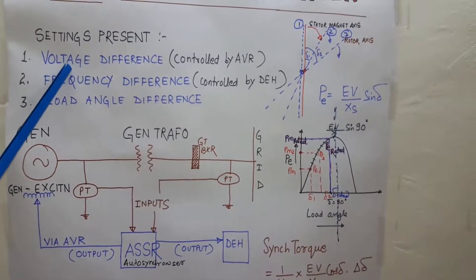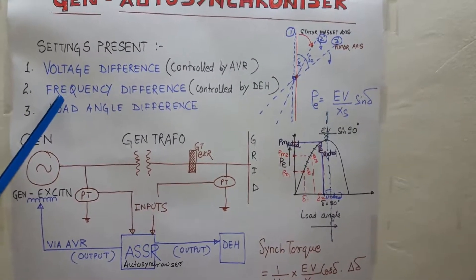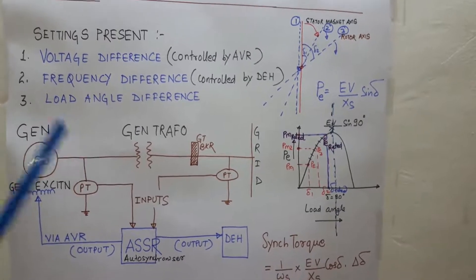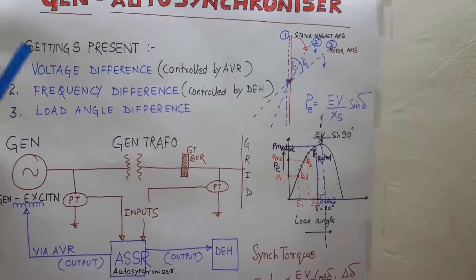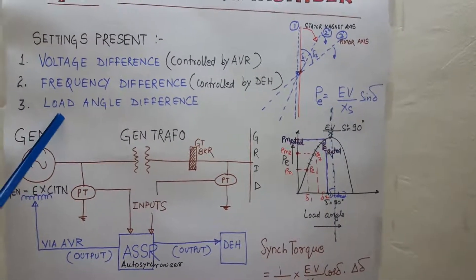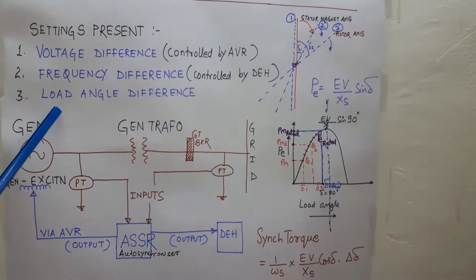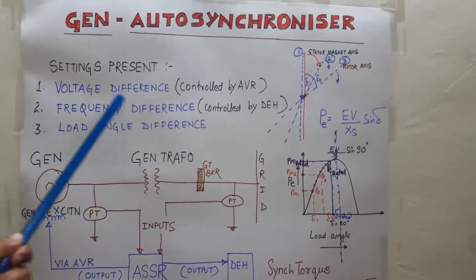One, the magnitude of the voltage. Second, the frequency of the voltage. Third, the phase angle of the voltage. So it has three settings: allowable voltage difference setting, allowable frequency difference setting, and allowable load angle difference setting.